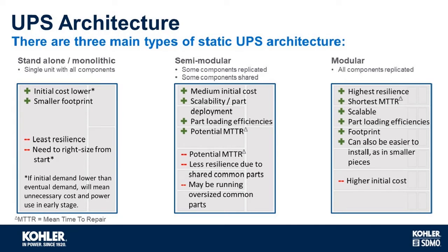With the semi-modular, you have a medium initial cost. It's partly scalable because some of the components are replicated, and therefore part load efficiencies can be controlled. You have potentially quick mean time to repair on the replicated components, so there will typically be a modular type system that we can swap in and out on a hot-swap basis. But also, because there are shared components, some of those might have a longer mean time to repair because they are built in and have to be repaired on site and are not swappable. So because of those shared components, we do get some resilience problems there. And some of that has to be right-sized from the beginning as well.